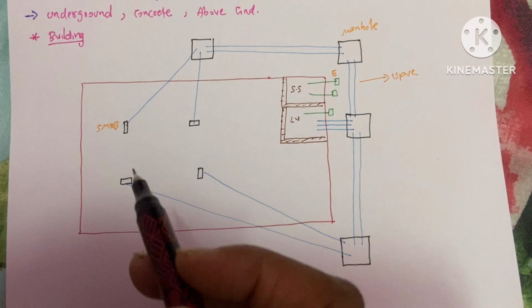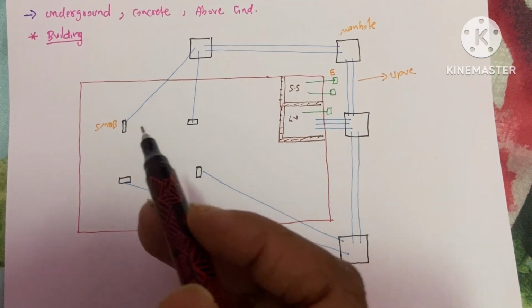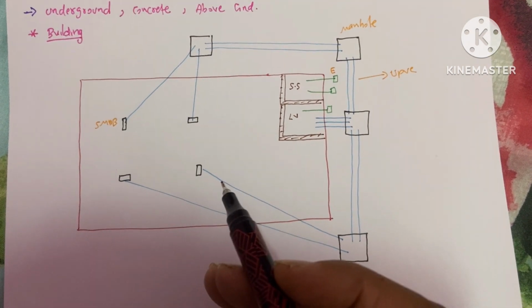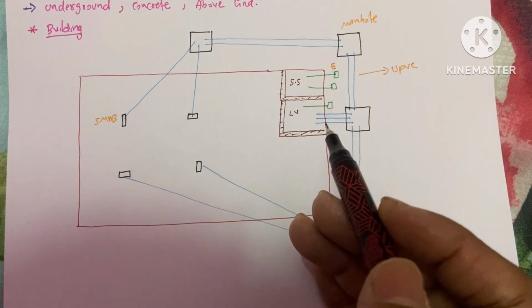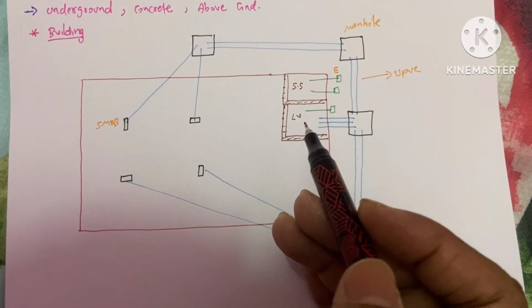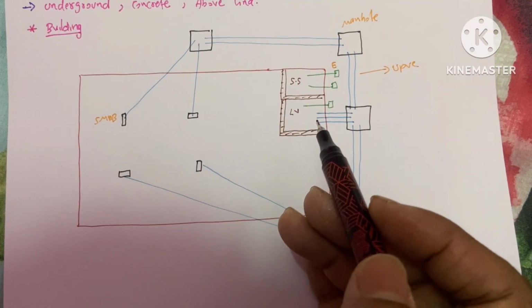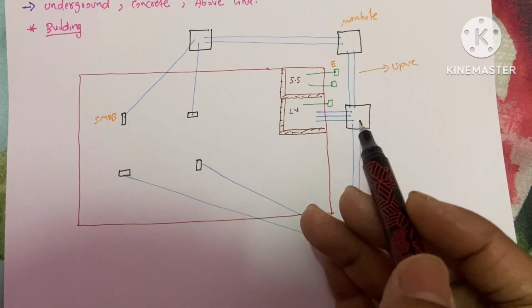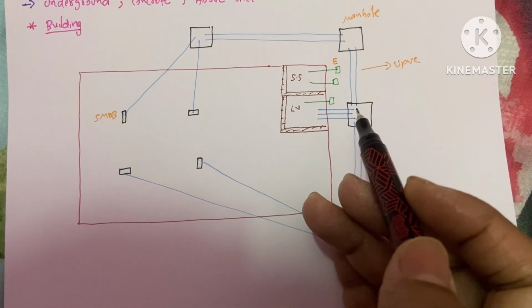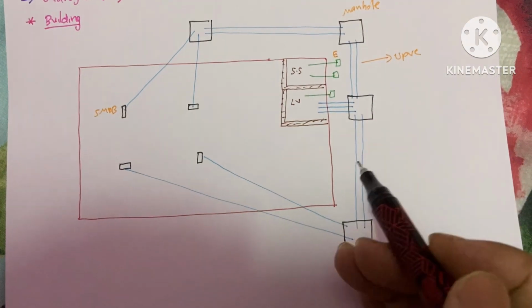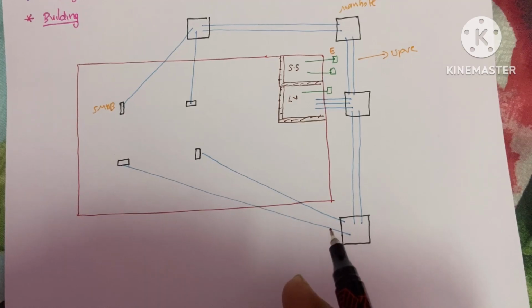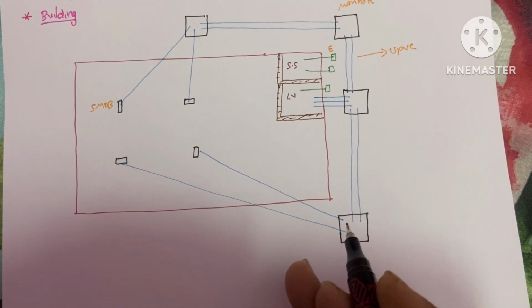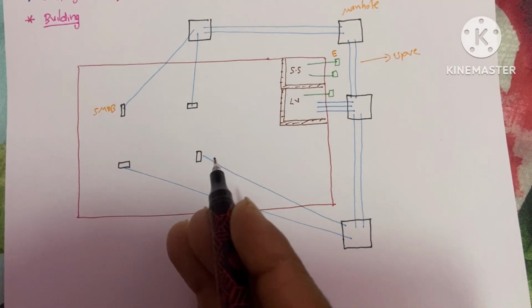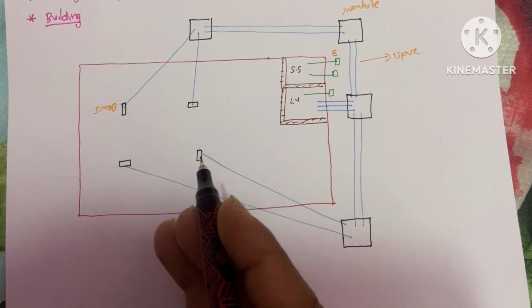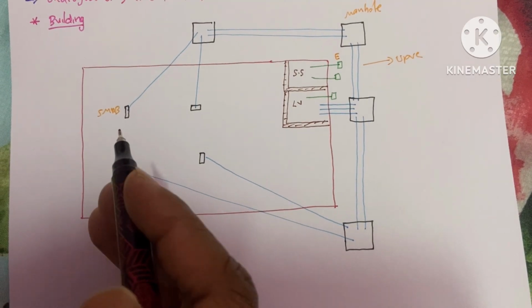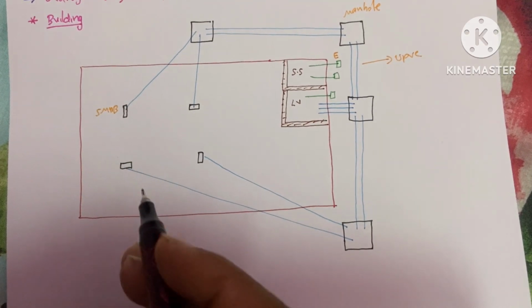These SMDBs require LV cables, and the cable is coming from this LV room. So first we lay UPVC ducts underground to the manholes, and from this manhole to another manhole like this. Finally, from this manhole we lay UPVC duct underground directly to the room which contains these SMDBs.